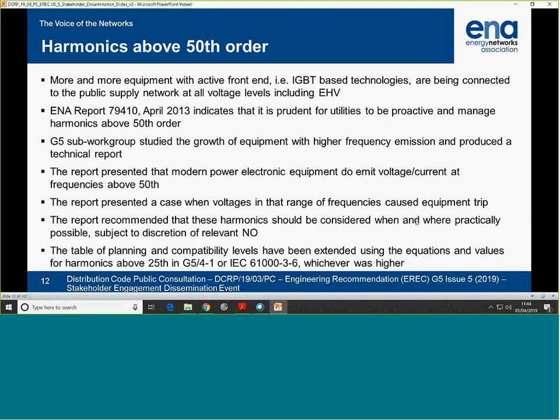So again, yes, we need to look at it, but with a caveat. That being that it will cost a lot of money to install appropriate transducers in the network. If you're monitoring harmonics above 50, you need equipment, money to do it, and you need transducers at voltages from LV to 400 kV. So it is at the discretion of the NO to say, yes, I need to assess this connection for harmonics up or low.